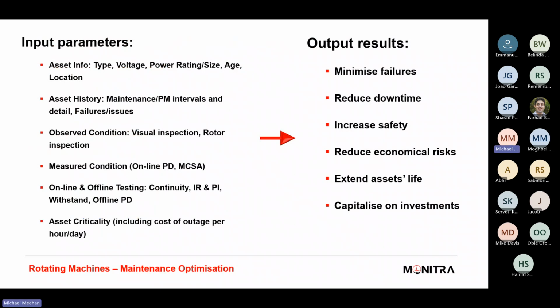So when we think of the way to develop the maintenance strategy plans, things that you want to look at, there's various input parameters which asset engineers are going to look at. These are probably the most common and critical input parameters. Obviously, you've got voltage rating. Higher the voltage, higher the stresses. A 3.3 kV machine may not be as concerning or high cost as, say, an 11 kV generator, 15 kV generator, or compressor motor on an LNG facility.